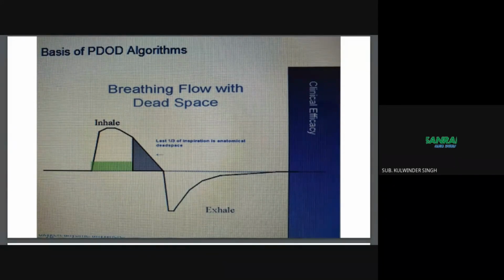So if the patient is taking 20 breaths per minute, then it is delivering 21 ml per breath. If the patient is taking 10 breaths, then it is doubled. It comes to the 42 ml per breath that it can deliver to the patient. So it matters if the patient's breath rate changes. So if we talk about the pulse flow machines in the market, there are various machines: Airsep, Focus, Freestyle 3, Freestyle 5, Eclipse, Inogen 1 G3, Inogen 1 G4, Inogen 1 G5, Philips Minigo, DeVilbiss based machines are also there, InvaCare XPO2.